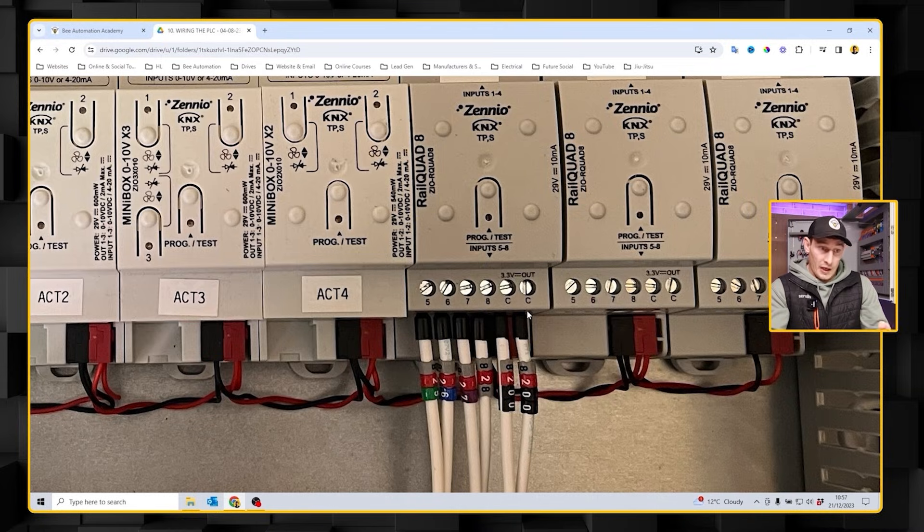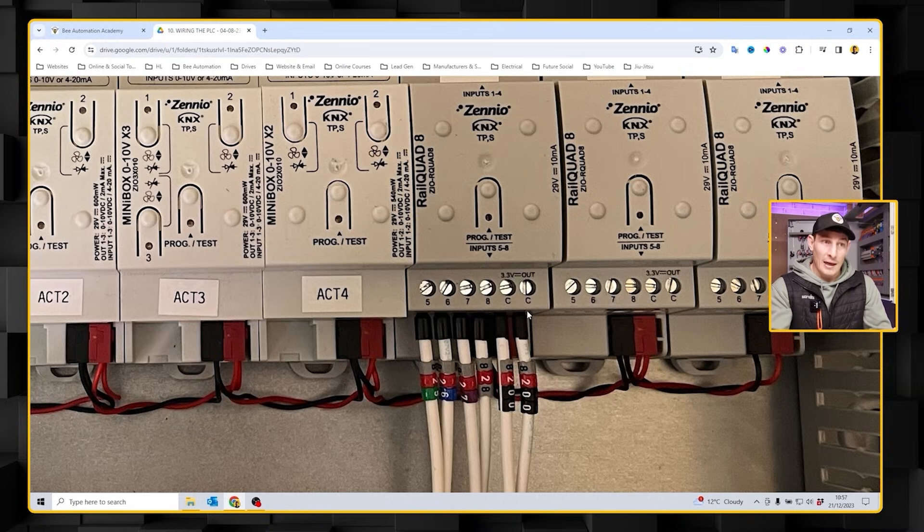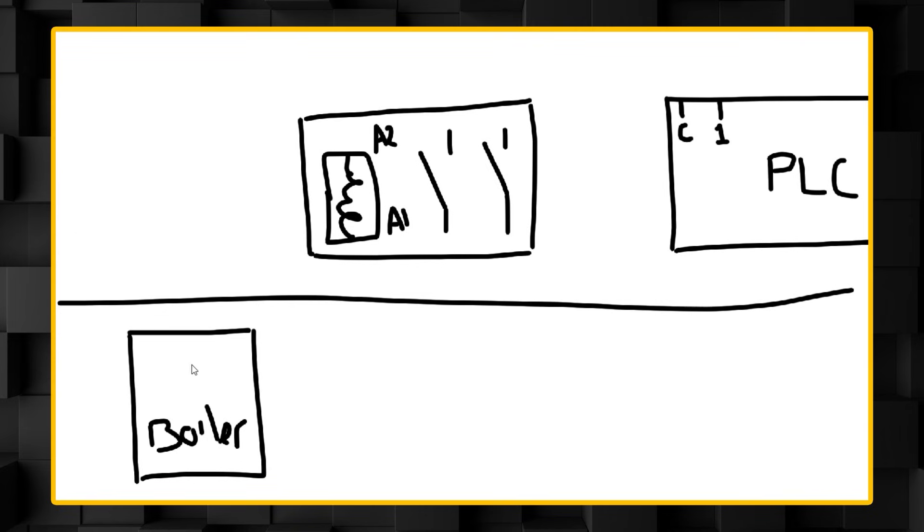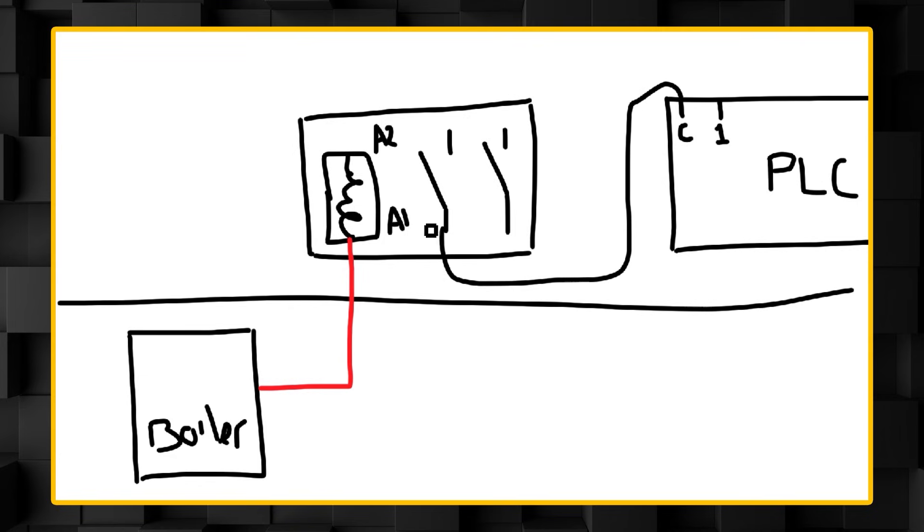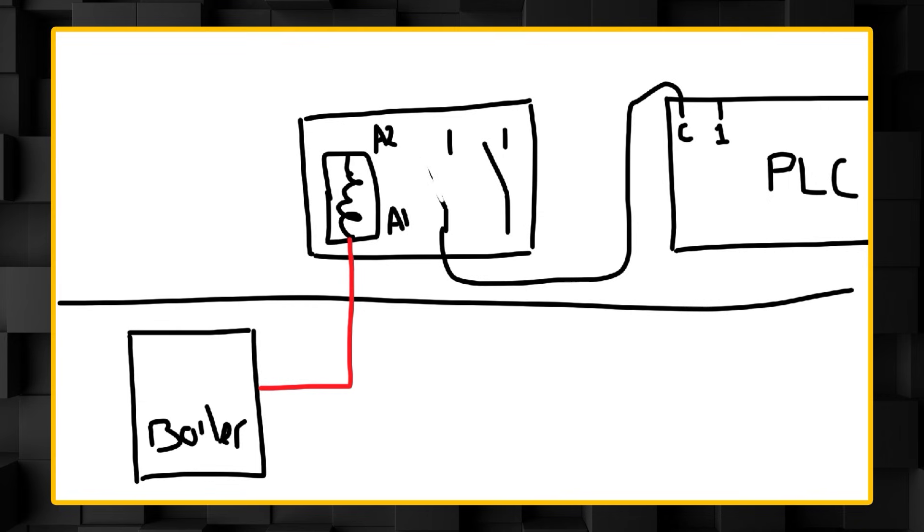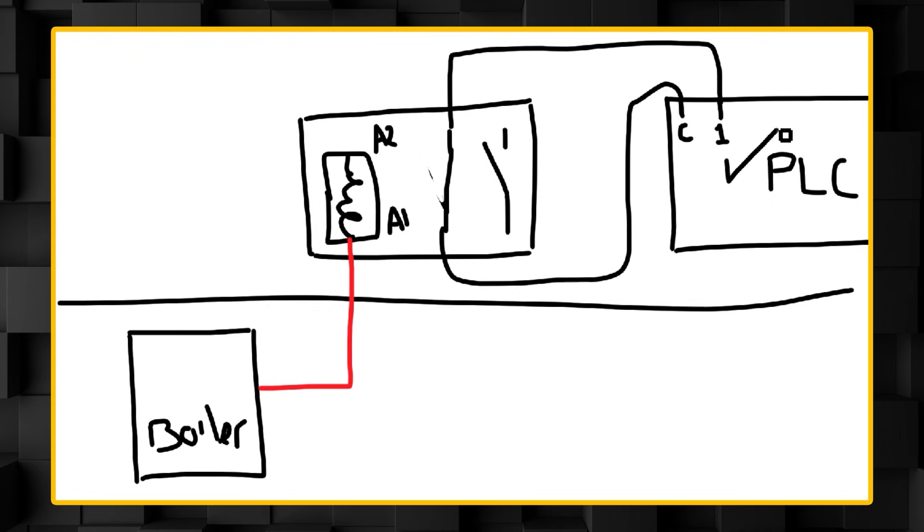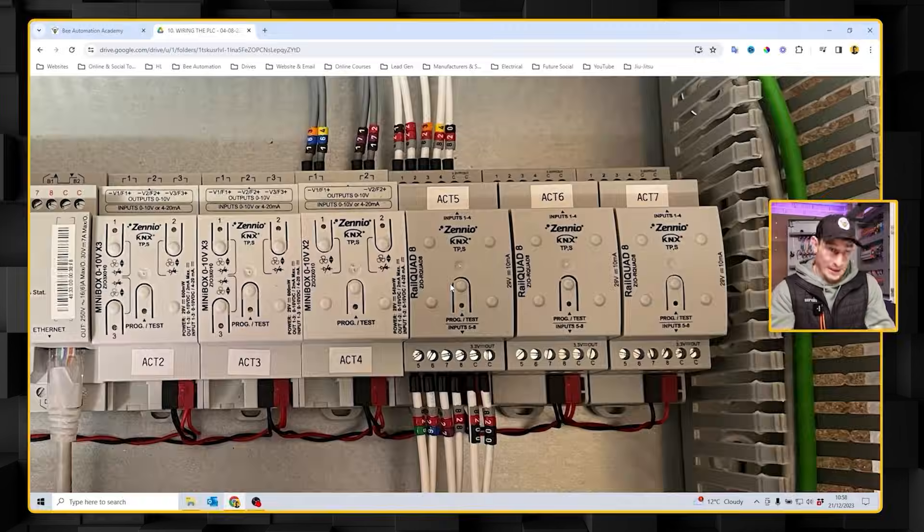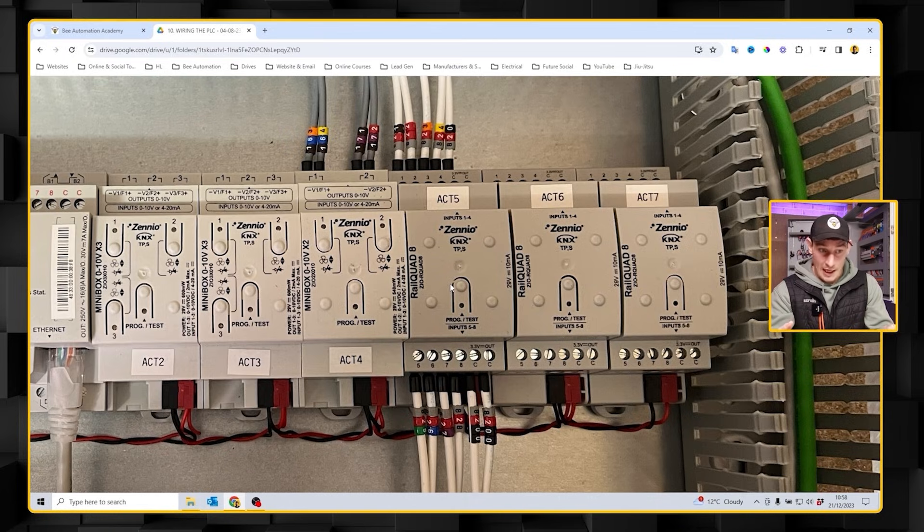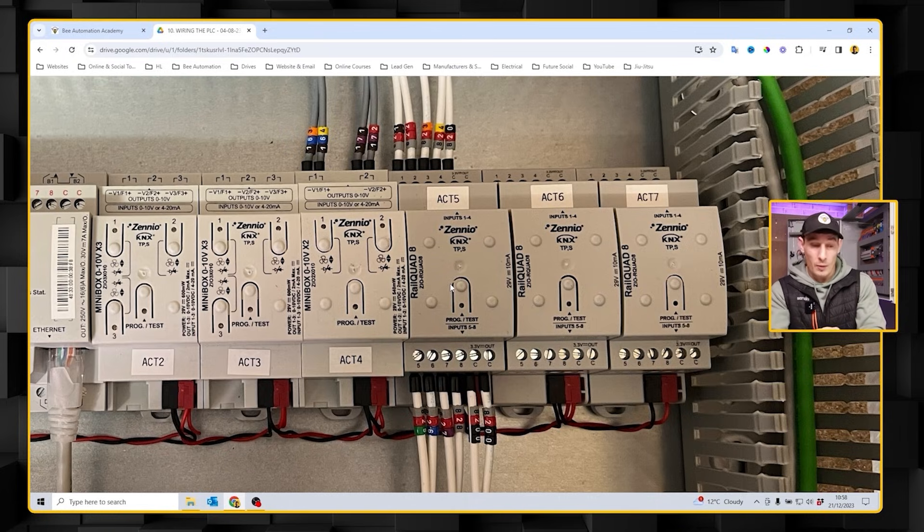But in the middle we've got a relay. In this project we're using a relay when a fault from the boiler occurs out in the field. That signal from the boiler energizes a relay in our panel, and one of the poles of that relay are these circuits. When that closes, that allows that common to go through the relay and back to the terminal. Our PLC can then see that there's a fault on the boiler and we can do whatever we want off the back of that, whether it's sending a text message, an email, or switching over to the other boiler.